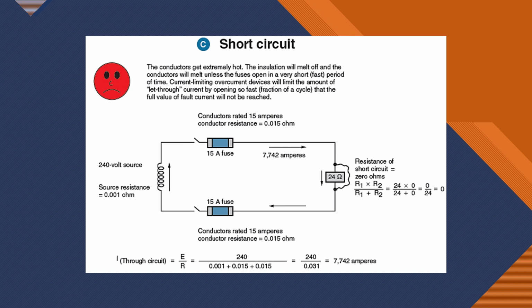I'm really just taking into account the resistance of the conductors with my voltage source, and that's going to leave me with 7,742 amps. So that's quite a bit. That 15 amp fuse should definitely blow. And selective coordination, we're going to get into that a little bit more, but selective coordination is what that's all about. When I hit 7,000 amps, what happens?